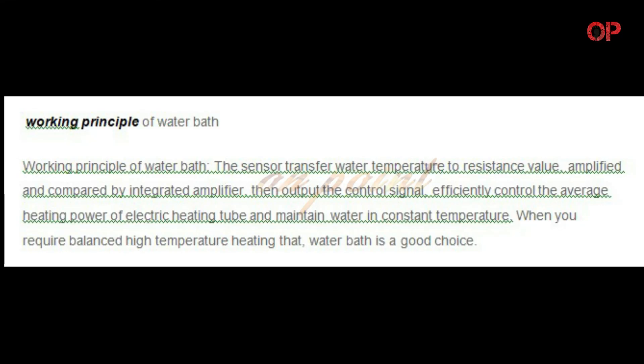Working Principle: The sensor transfers water temperature to a resistance value, amplified and compared by an integrated amplifier, then outputs the control signal, efficiently controlling the average heating power of the electric heating tube, and maintaining water at a constant temperature. When you require balanced high temperature heating, a water bath is a good choice.